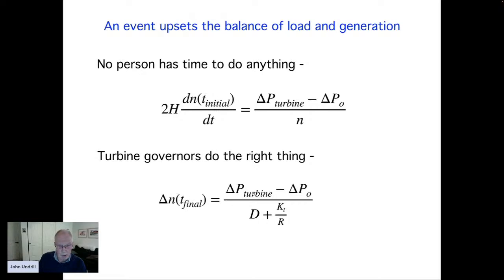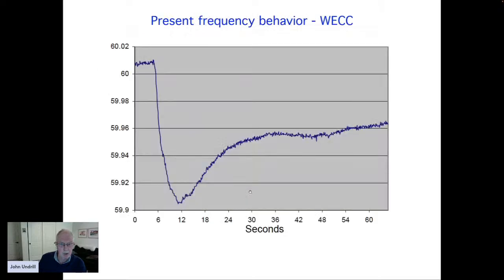The speed and the frequency settled as required by the droop equation. Here's such an event, not in simulation, but in reality. This is the frequency of the Western USA grid over a minute from 0 to 60 seconds when a large generator tripped off the line. This was a very large generator.